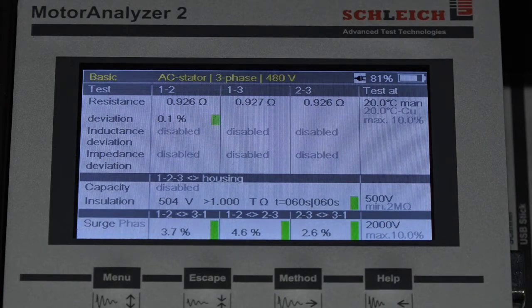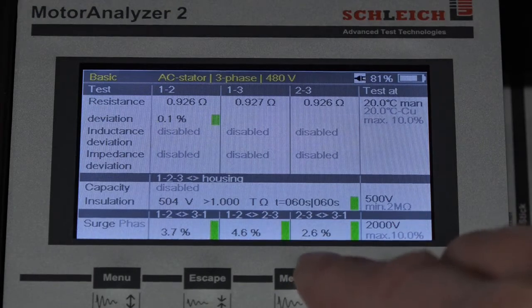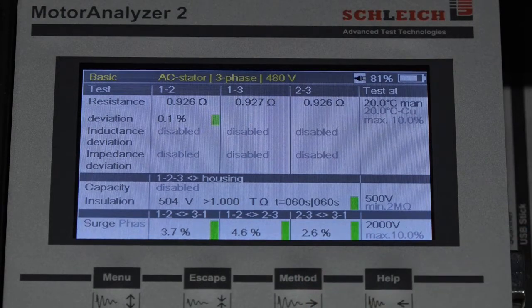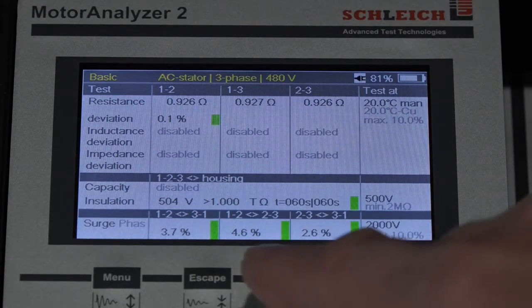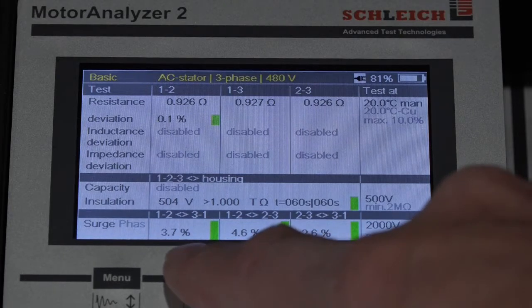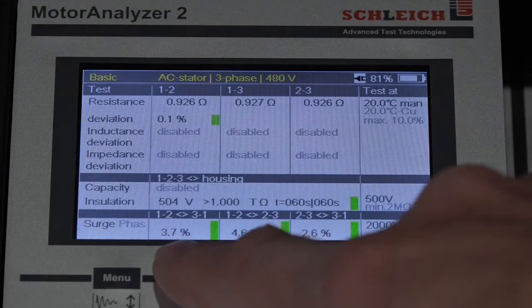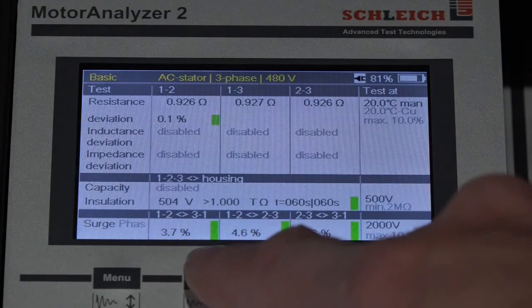Now, surge testing a stator is actually pretty easy. You actually only need to apply 3 pulses to the stator. 1 pulse between lead 1 and 2, a second pulse between 2 and 3, and a third one between 3 and 1. Once it has those 3 waveforms, it will calculate the line-to-line or phase-to-phase error area ratio between the first waveform and the one between 3 to 1.